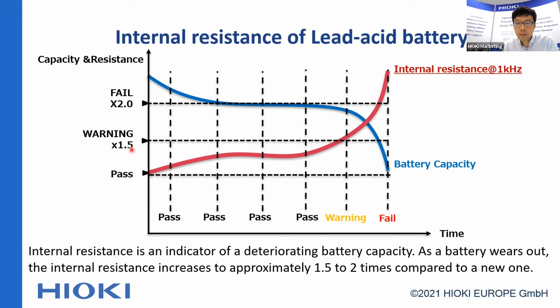Here is an example. If battery resistance exceeds 1.5 times the initial value, you should start planning to replace the battery cell. If it's more than 2 times the initial value, you should replace it with a new one right away. So this 1.5 and 2 are just reference values, and this threshold depends on the battery type.